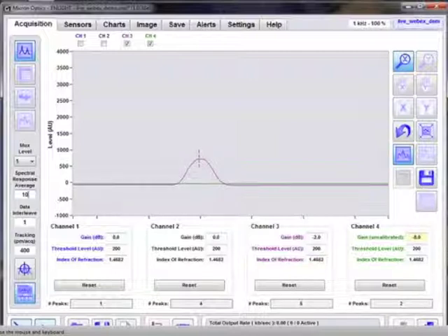So average judiciously. There isn't a control on how many averages can be taken, but you do need to be aware of the impact, as Dan said, on memory usage, as well as the impact on time response of the system. Here you can see that there's an appreciable reduction in noise with just 10 averages on the spectral trace. But again, in the case of the SM130, that's largely aesthetic.